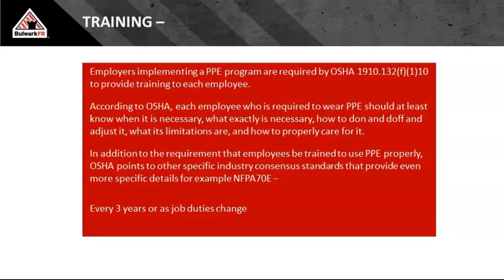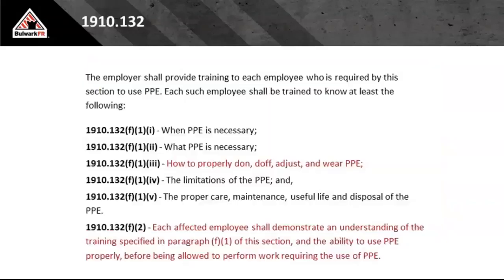Training, very key, very important. 1910.132 walks you through all the things you need to do. 70E says train them every 3 years on their arc flash PPE and/or as their job duties change. If you go from unqualified to qualified, if you're new to the job, if you switch departments, new training is required. 132 tells you when PPE is necessary, what PPE is necessary, how to properly don and doff it.